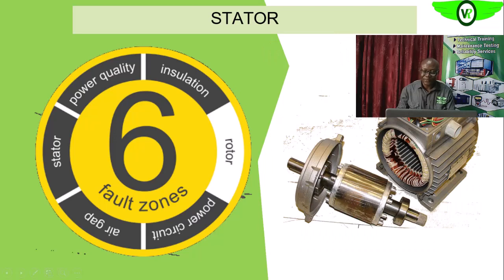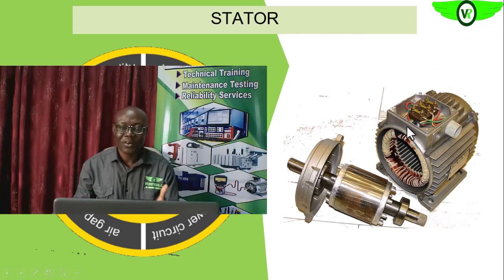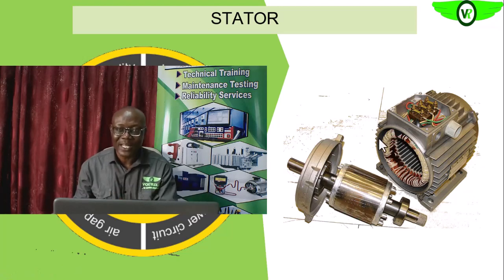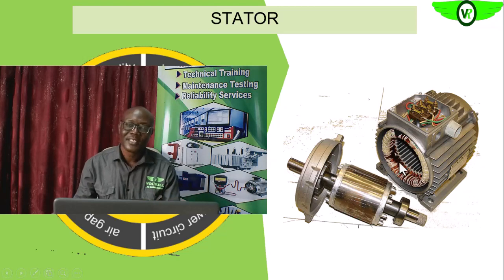So the stator itself, like we also said earlier, we have the windings, okay, so we can do the low resistance tests on each of these windings, or we can do the inductance tests. Are we getting it? To see if there are any unbalance. Okay, remember, unbalance in the resistance will affect the voltage, can also introduce voltage unbalance that will eventually affect the operations of the electric motor. So that is what we will do.